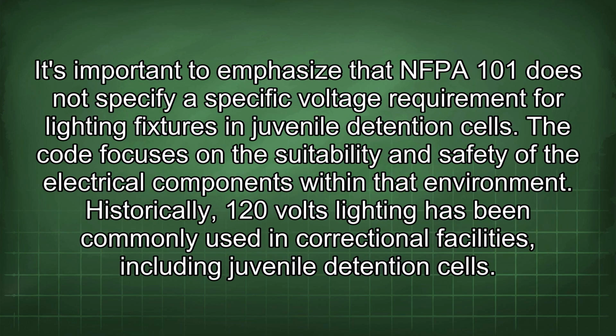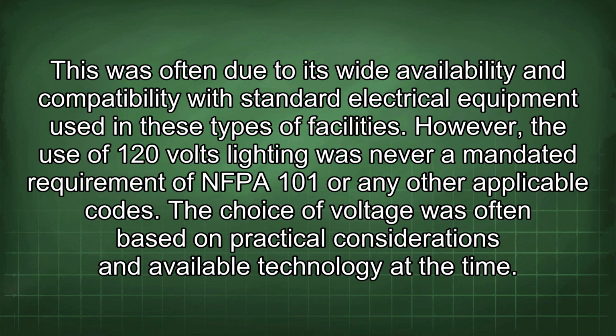It's important to emphasize that NFPA 101 does not specify a specific voltage requirement for lighting fixtures in juvenile detention cells. The code focuses on the suitability and safety of the electrical components within that environment. Historically, 120 volts lighting has been commonly used in correctional facilities, including juvenile detention cells. This was often due to its wide availability and compatibility with standard electrical equipment used in these types of facilities. However, the use of 120 volts lighting was never a mandated requirement of NFPA 101 or any other applicable codes. The choice of voltage was often based on practical considerations and available technology at the time.